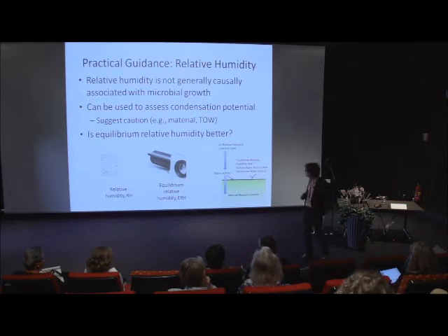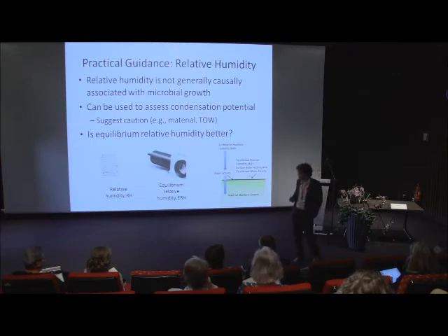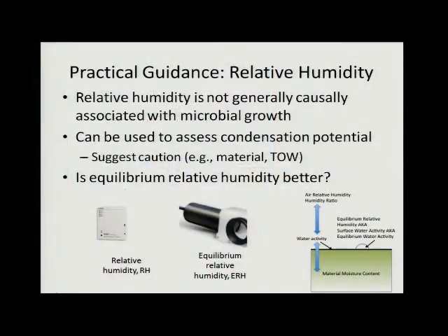So a short excursion above your threshold relative humidity is probably not a big deal. And some materials can tolerate quite high relative humidities for a long period of time. So what that pushes me towards is this idea of equilibrium relative humidity. Is this a better measure?